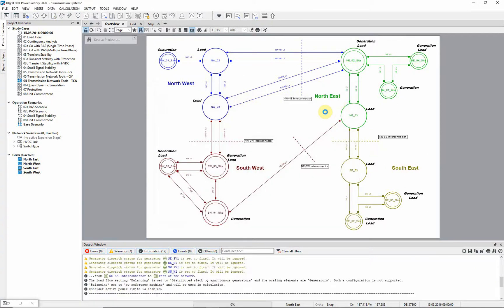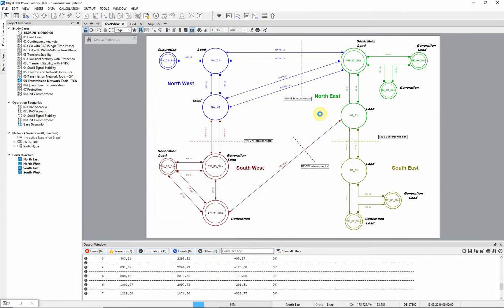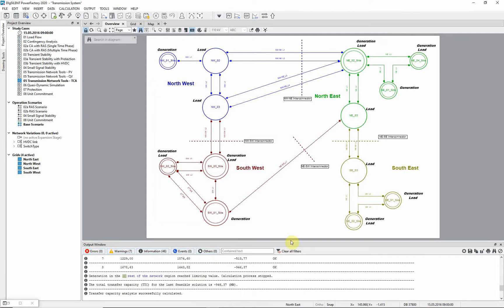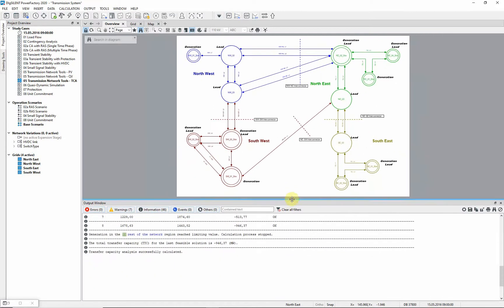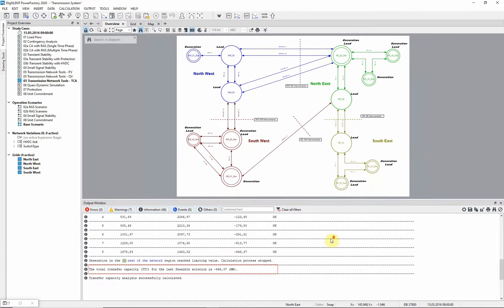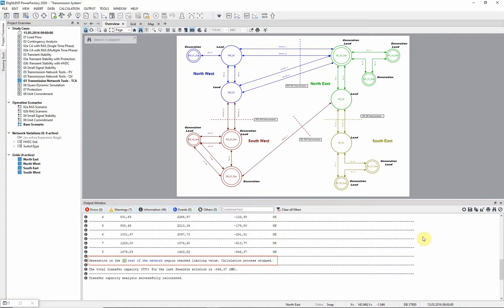The analysis is executed and we can see in the output window that the total transfer from the south east to the rest of the network has a limit of about 946 MW. No thermal ratings have been exceeded, the transfer limit has been found when no more generation can be scaled down in the rest of the network.